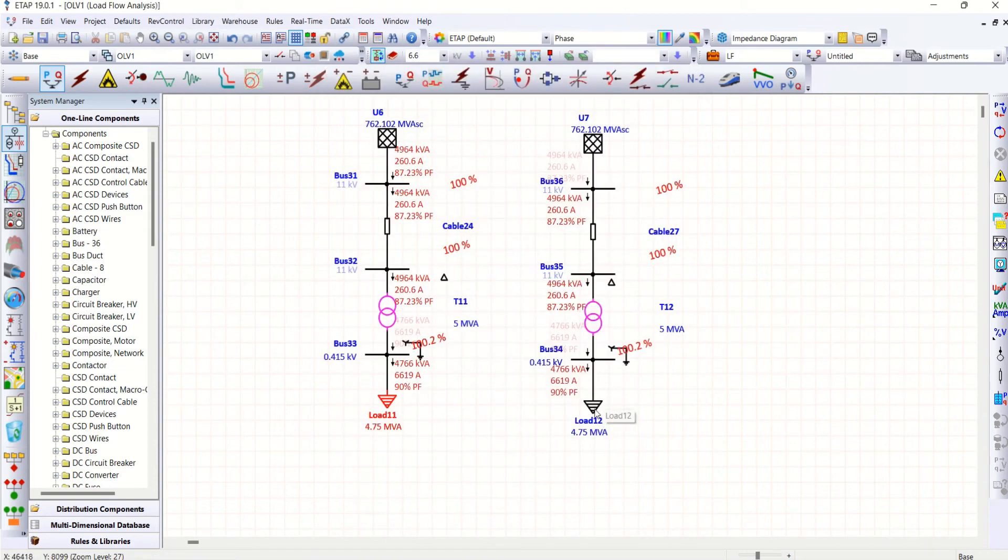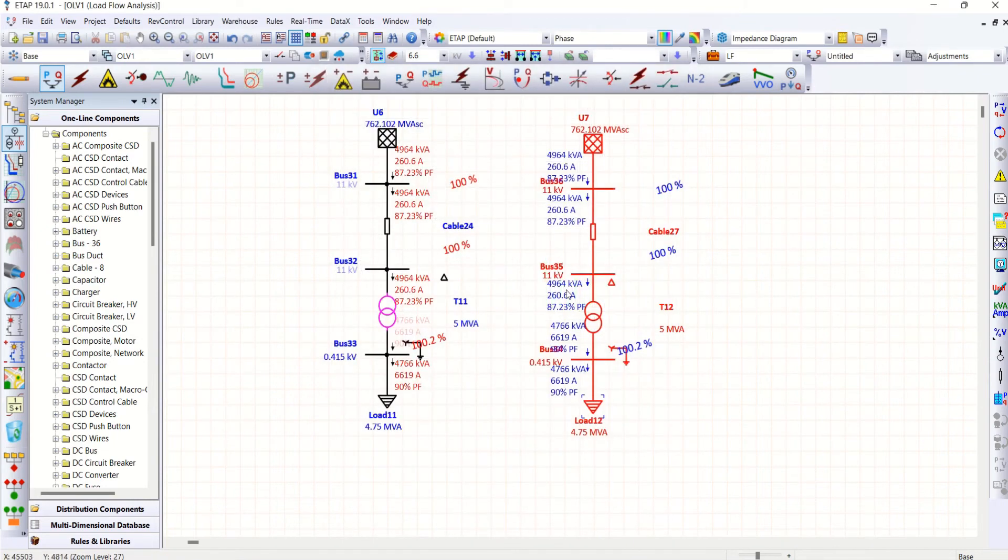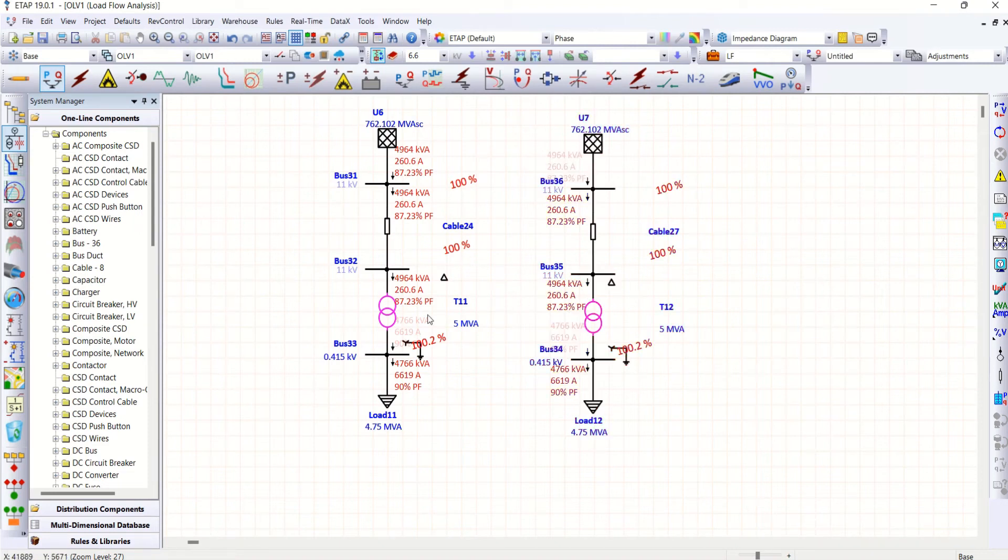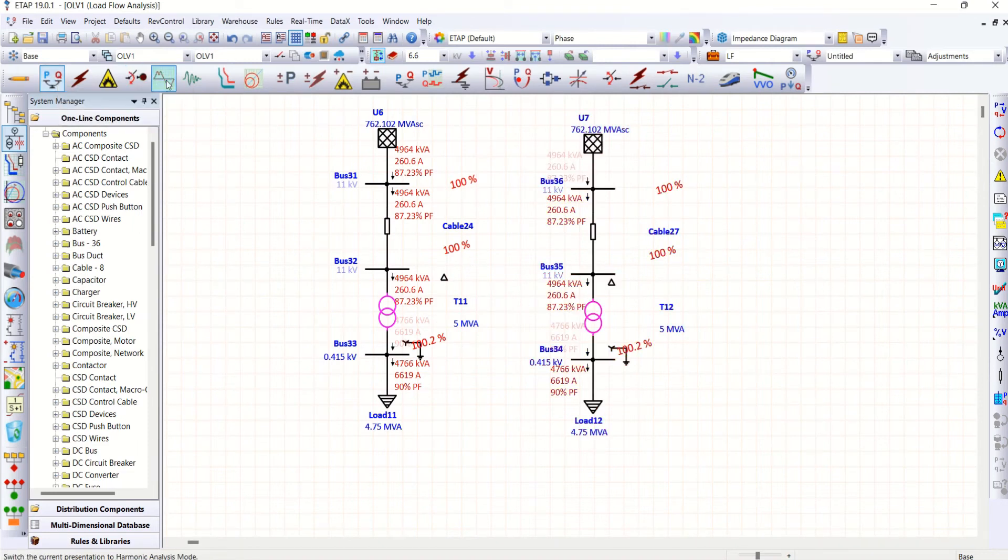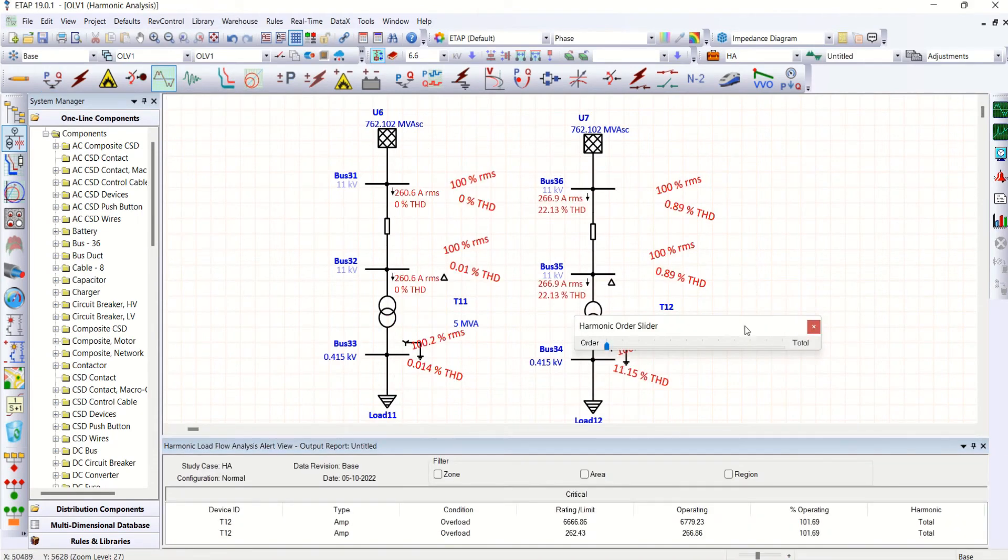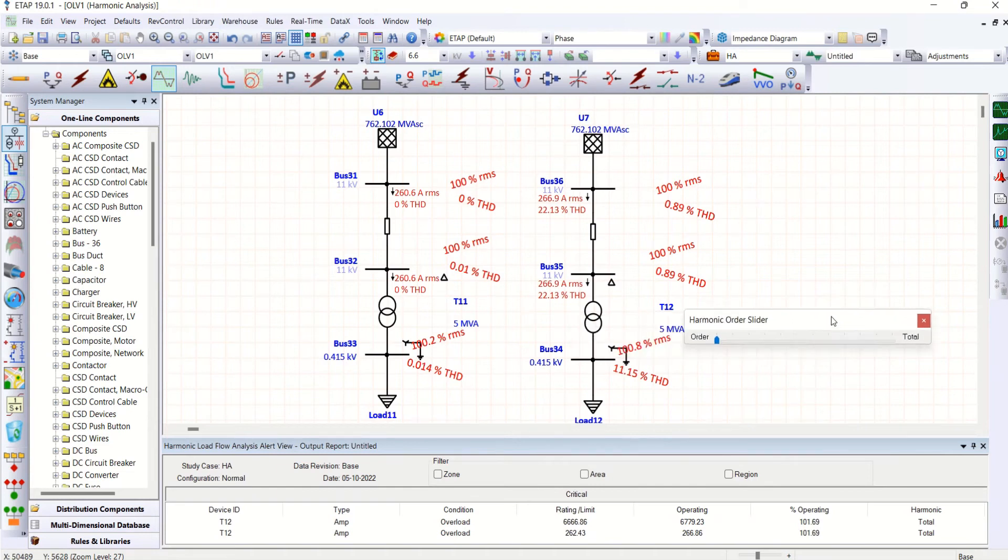On load 12, this side, we have harmonic injection. So even though harmonics injection here is showing only 260.6. Reason is I'm running only load flow. Now let me go for harmonic load flow. Let's see the difference.